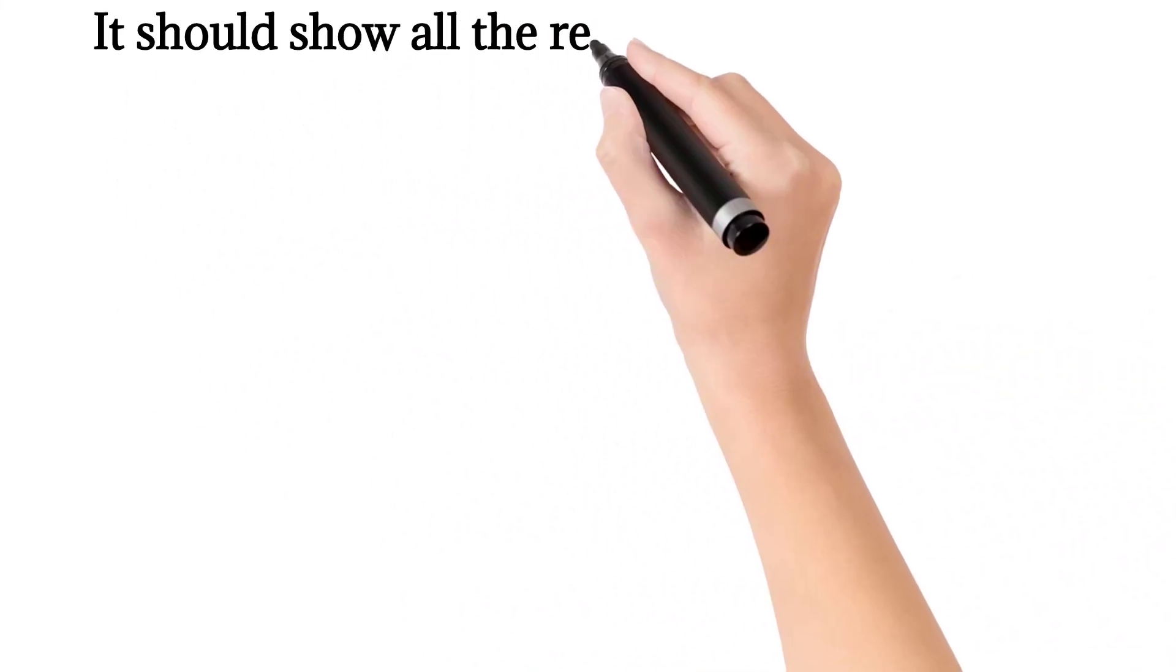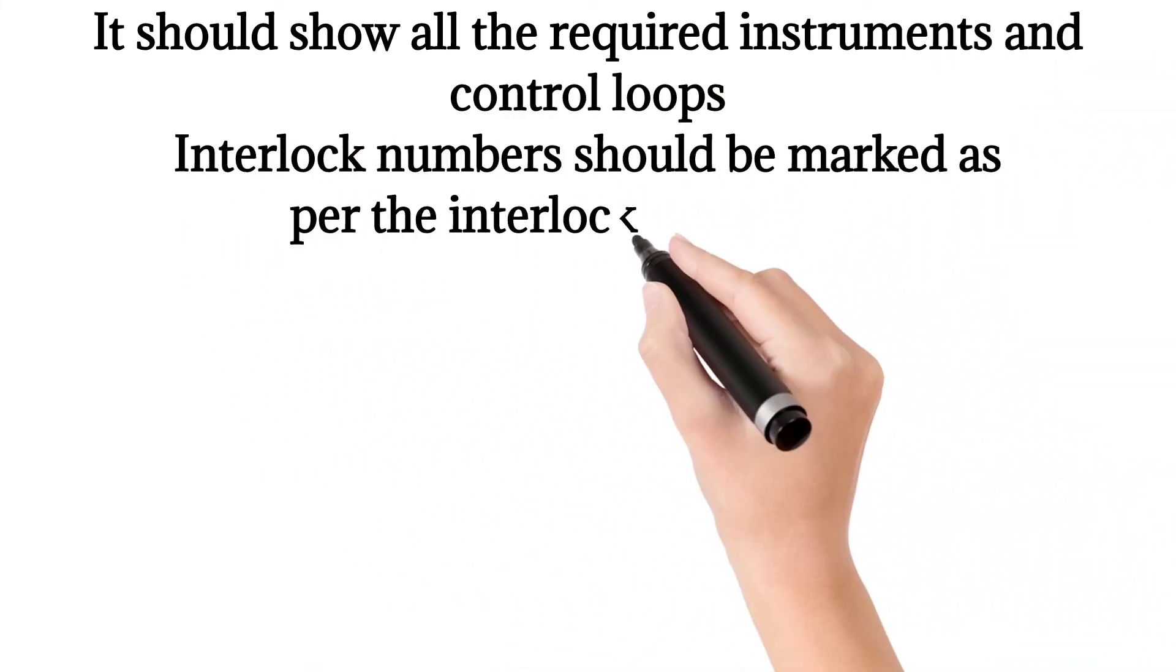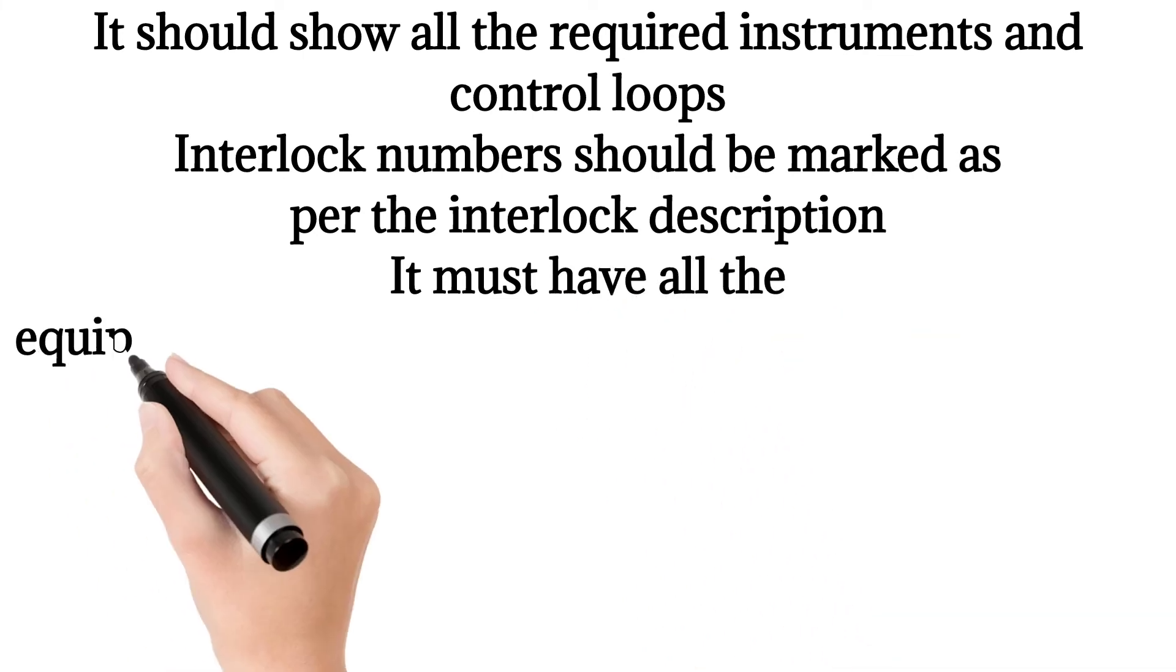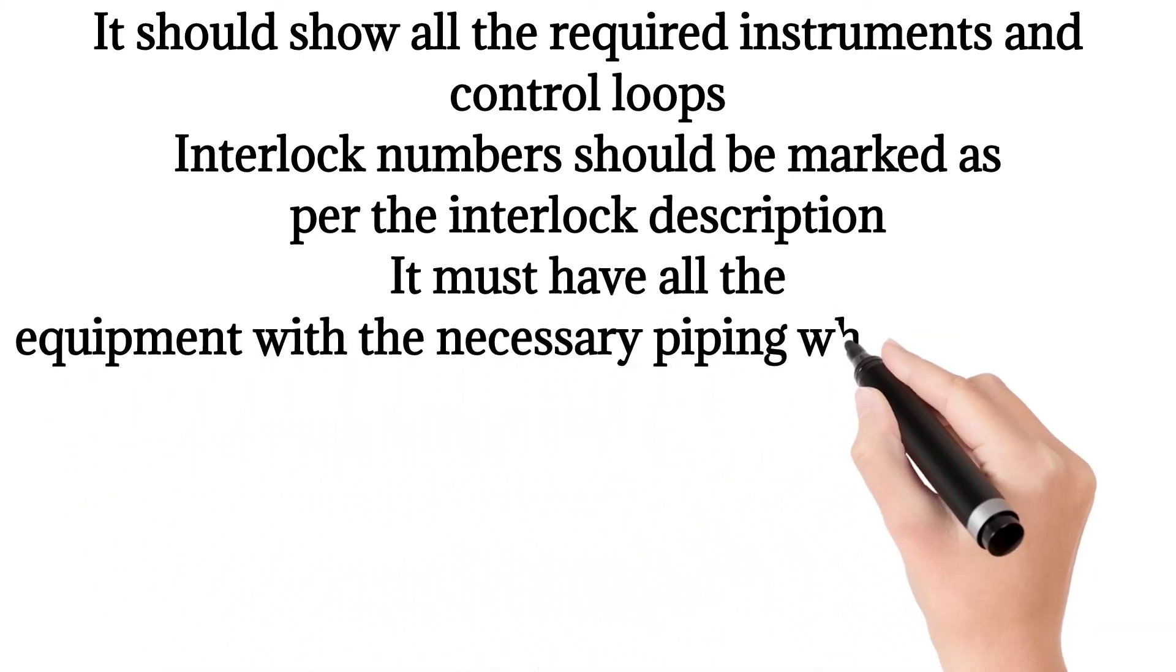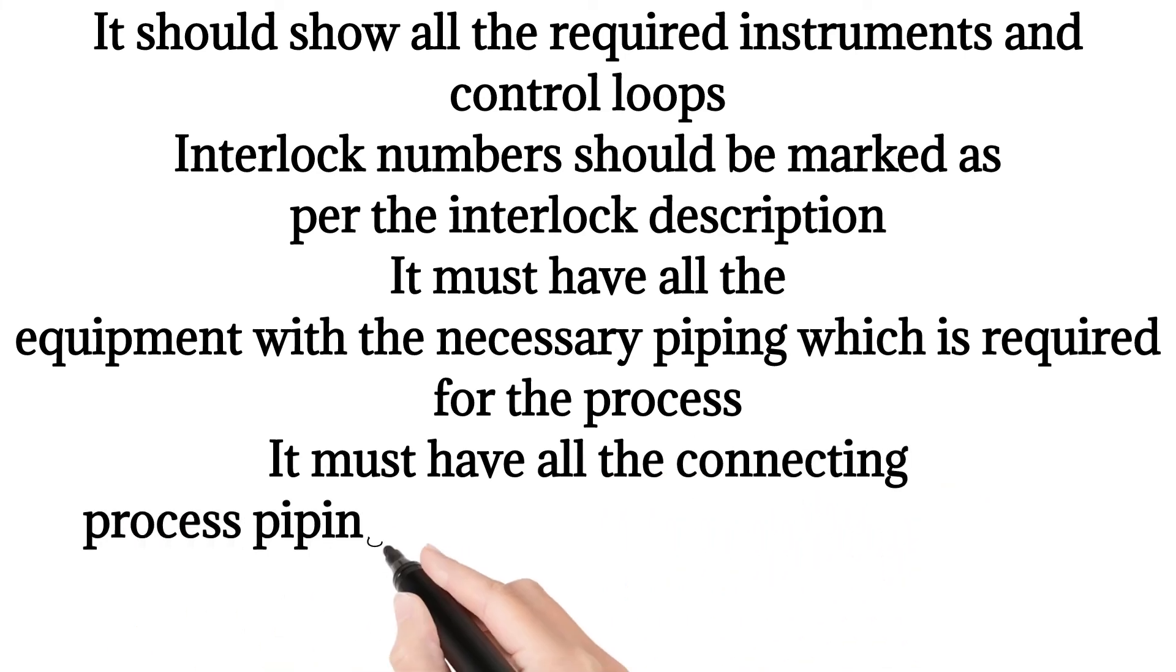It should show all the required instruments and control loops. Interlock numbers should be marked as per the interlock description. It must have all the equipment with the necessary piping which is required for the process. It must have all the connecting process piping which is required to carry out the process.